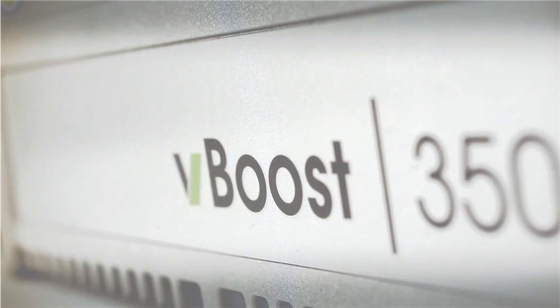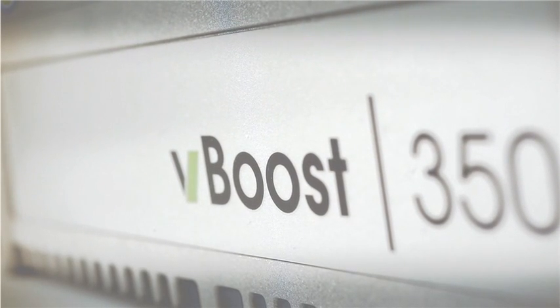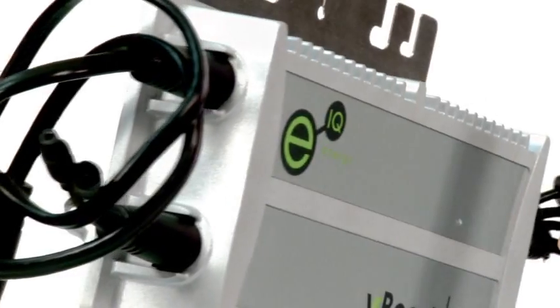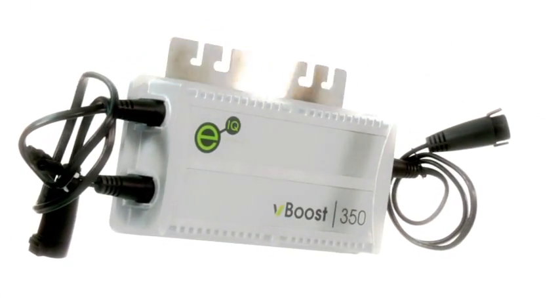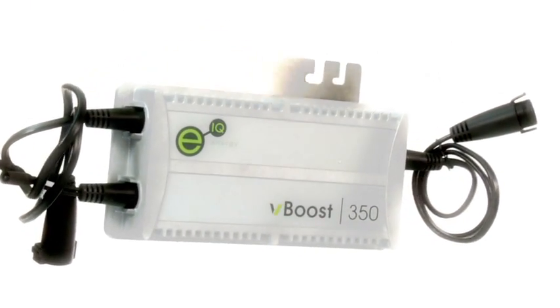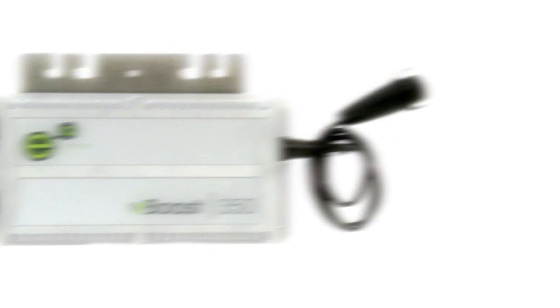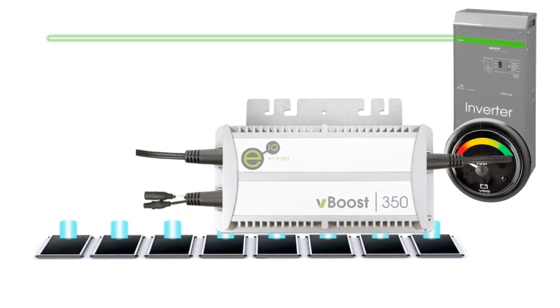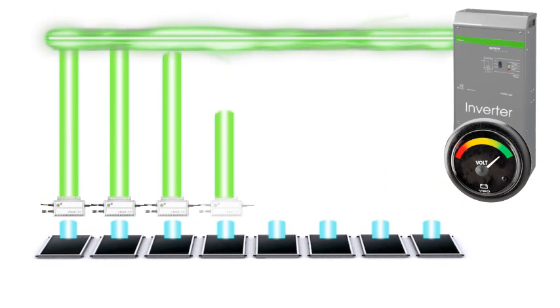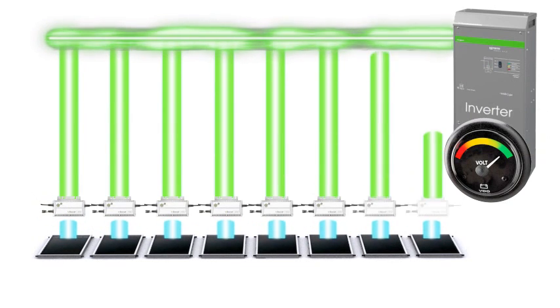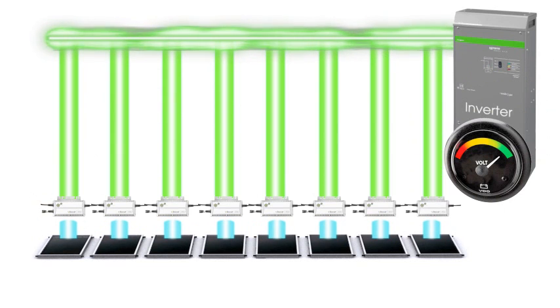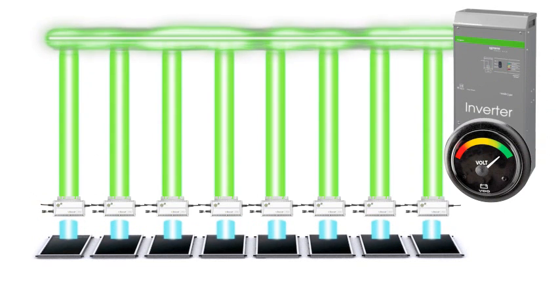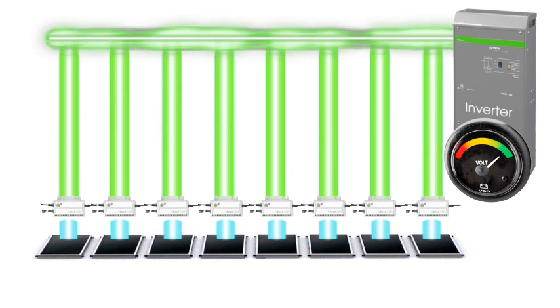The VBoost module changes all of this by enabling parallel architecture, which resolves these design limitations. The VBoost module takes the voltage from the module and matches it to what the inverter wants by boosting it to a constant DC voltage. Each module becomes its own independent contributor to the array's power bus.